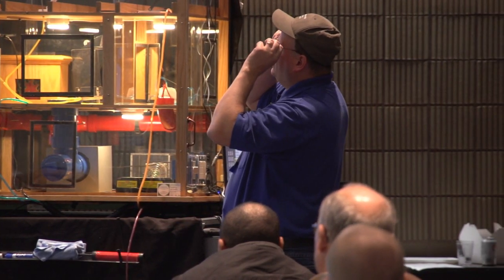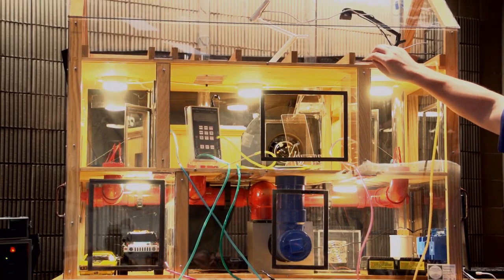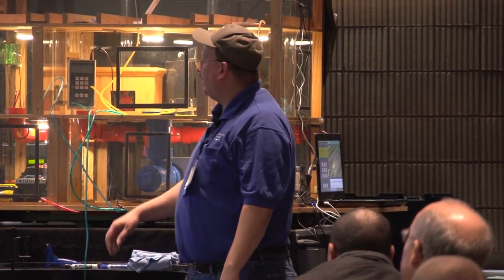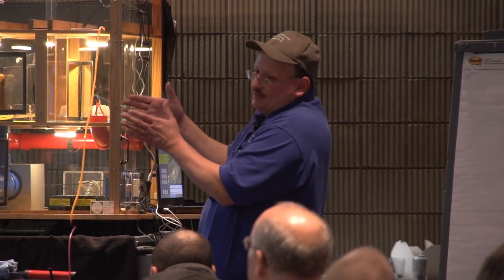My house is at 50, thereabouts. My attic's pretty close to 52. What does that tell me about my attic? That it's basically all the way outside, right? So when I open that attic access, what do you think is going to happen to the attic pressure? It's going to drop. Now, my house is at 50. I made a leakage. I made one big leak in the attic. Looking at that number right now, what can you tell me about the attic on that B side reading? Reading 25, is that inside or outside? It's about half and half, isn't it?